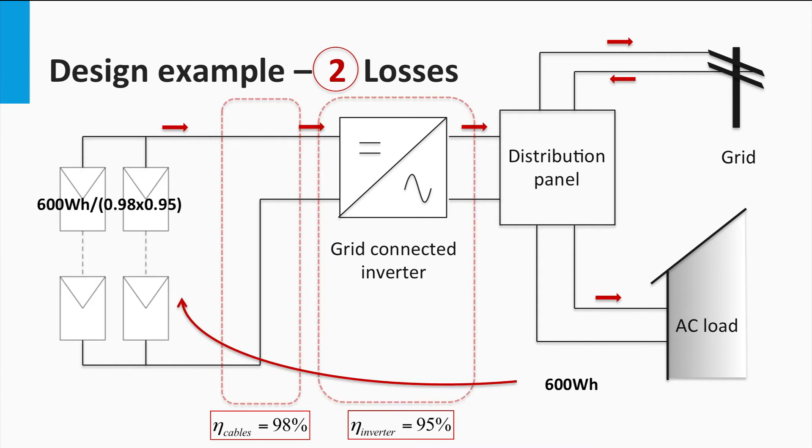Given the system component efficiency, we can then calculate the equivalent energy required from the PV panels as shown. This is basically nothing but the transposition of the energy before all these losses occur. Therefore, the total energy requirement for the PV array is 644.5 Wh.